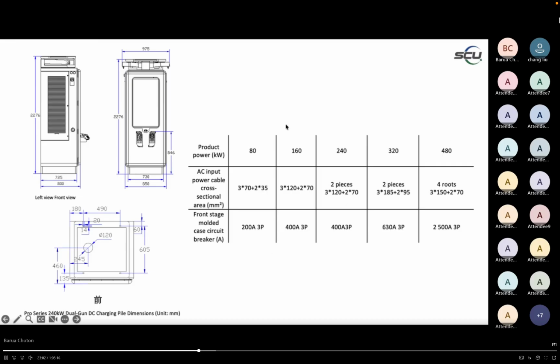For 240 kilowatts, we use a 400 ampere circuit breaker. As power increases, we use 2 pieces of 500 ampere circuit breakers for the 480 kilowatt EV charger. So that was the information about the platform, how the cables go inside the EV charger, the dimensions, and the different cable specifications needed for different power levels.